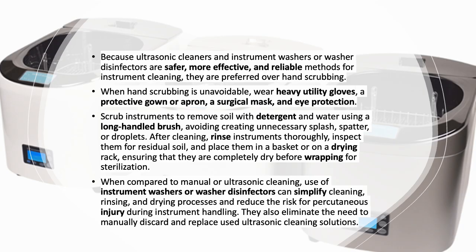When we compare the instrument washer or washer disinfector with ultrasonic or manual cleaning, we find it's simpler in the cleaning, rinsing, and drying process. And also, it reduces the risk of percutaneous injury during instrument handling. Also, it eliminates the need to manually discard and replace the used ultrasonic cleaning solution.